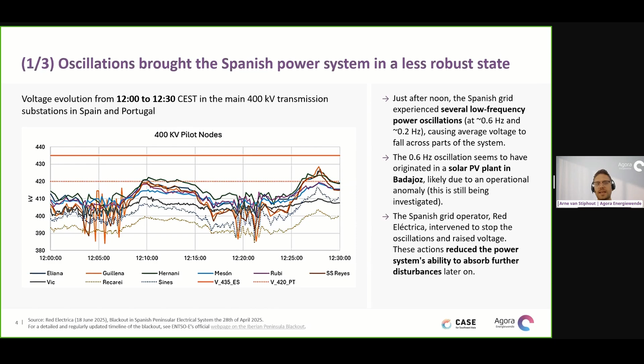The 0.6 hertz oscillation is worth pointing out. It seems, though this is not yet fully confirmed, to have originated in a solar PV plant in the south of Spain, likely due to an operational anomaly. Now, the Spanish grid operator intervened to manage these oscillations. These are things that they commonly do, especially the second oscillation, which is a common occurrence, or at least a well-known phenomenon, in the European grid. And they took these actions to mitigate this. But what this did was reduce the power system's ability to absorb further disturbances later on.